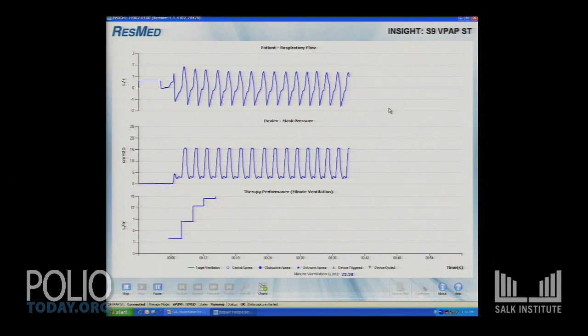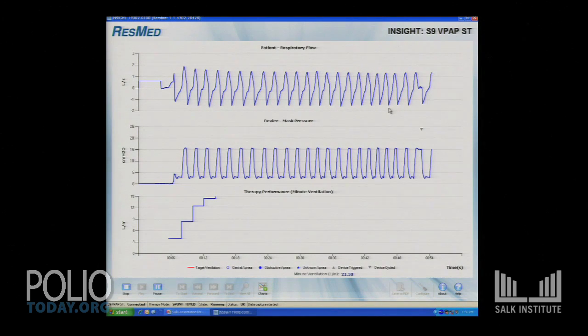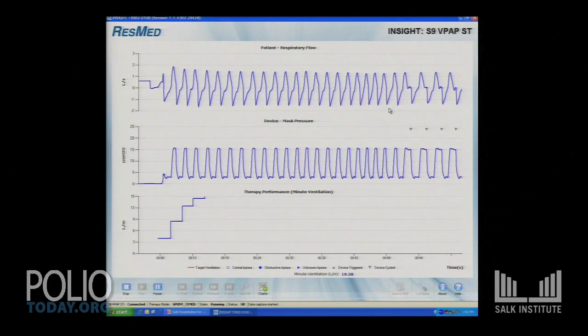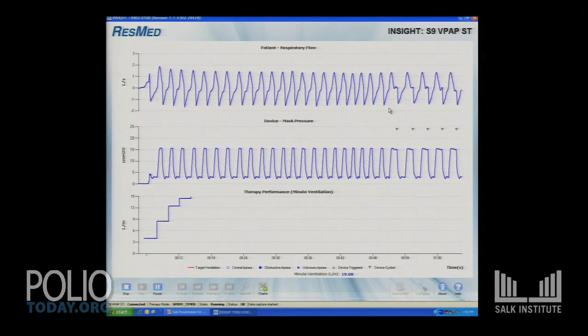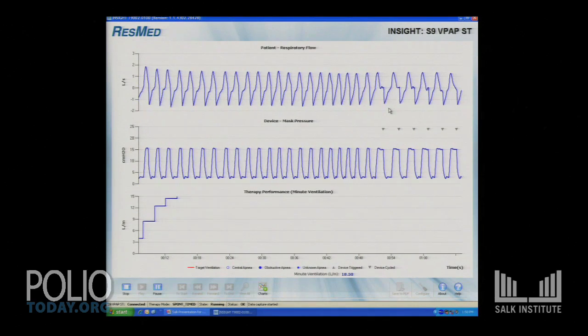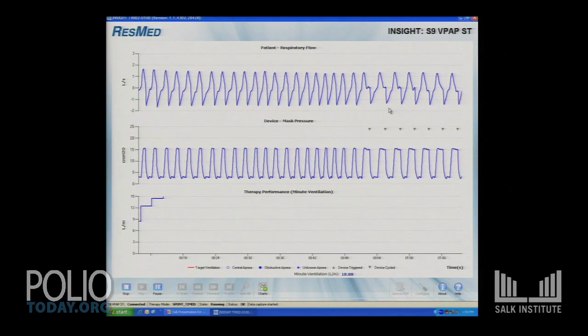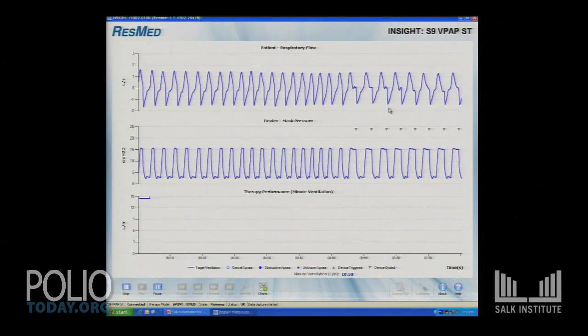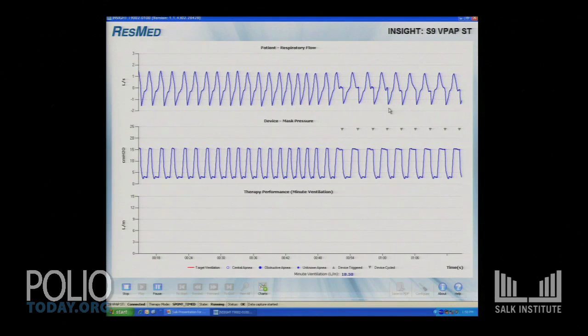The respiratory therapist can look at that and say, you know what? I'd like him to have a little bit longer time for gas exchange. So what we're going to do is set a TI minimum, and I'm just guessing here on where to set that. Perfect. Can you see the difference instantly? You see? Now the machine is telling me here that TI min is active, as if I couldn't tell just by looking at the difference. See how quick this breath was and how this one is elongated. He has more time there for gas exchange.